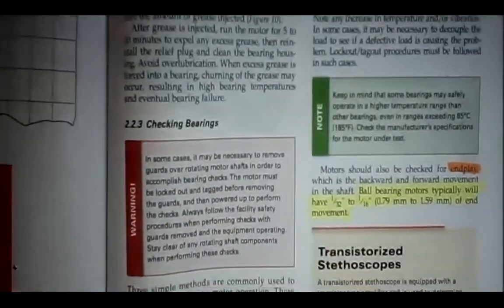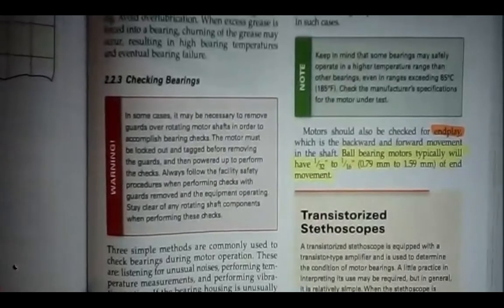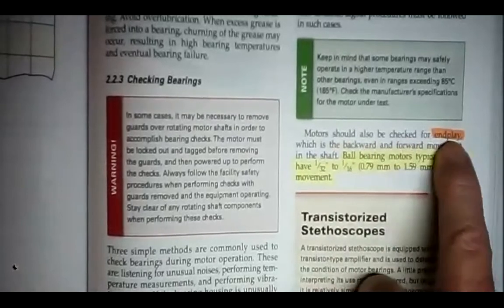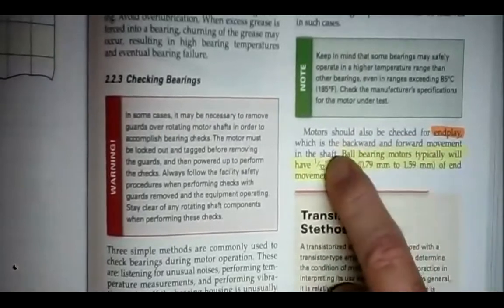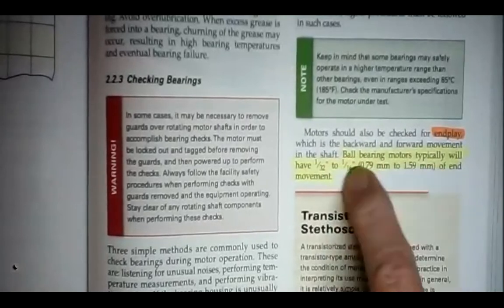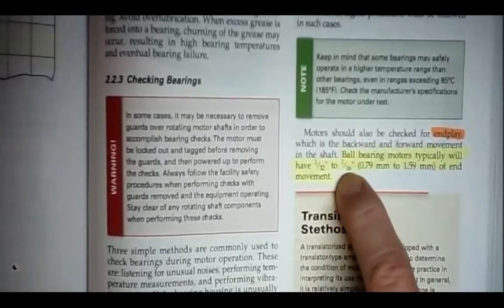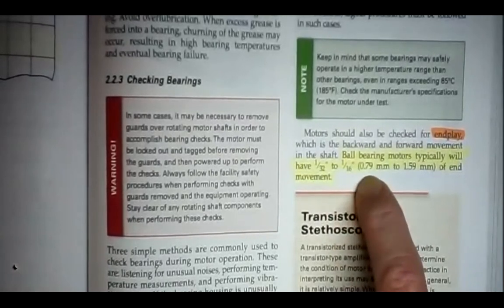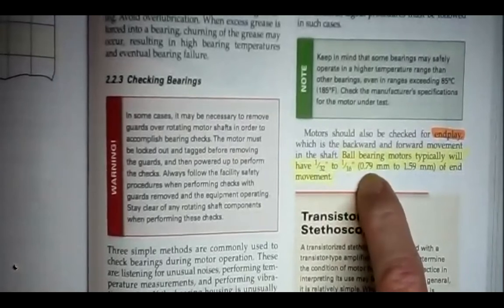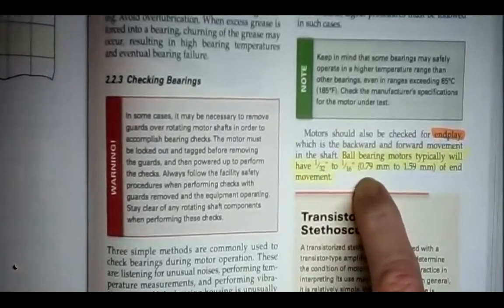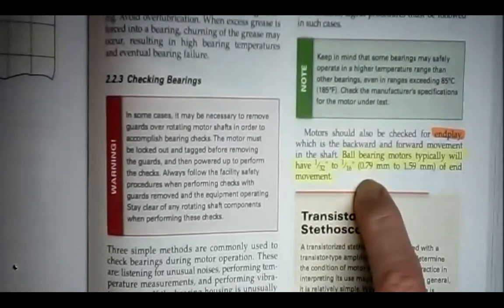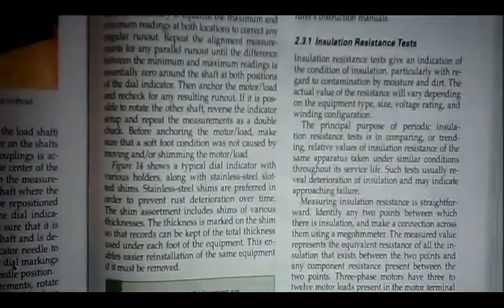On page 13, on the right-hand column, they're talking about end play. Motors should also be checked for end play, which is the backward and forward movement in the shaft. Ball bearing motors typically will have a 32nd to a 16th of an inch of end movement. In other words, if you grabbed the shaft of the motor, you could physically move it in and out, a 32nd to a 16th of an inch, it'll move. That end play is not a bad thing. Don't think of it as being harmful to the motor. It has a little bit of end play, and that's a good thing.